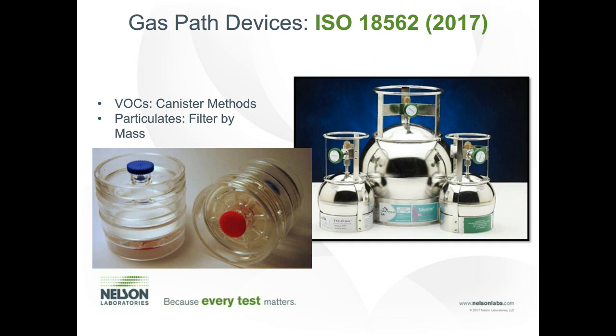For the particulates, there are a couple of different ways this can be addressed analytically. There's a really common method for measuring particulates that's more often used in the environmental industry, but basically you run the device again in worst case and direct all of the output through a filter, and you can measure the filter by mass and determine if there are any particulates coming through. For the condensate, that can be captured with extractable leachables chemistry testing.